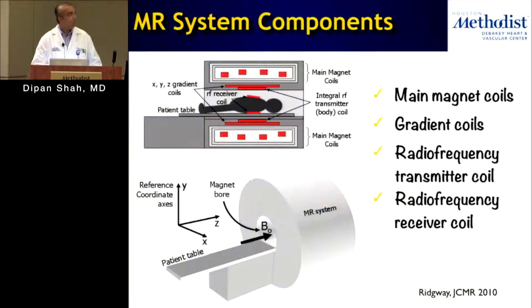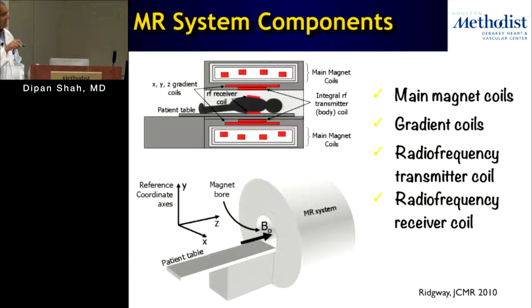I'm going to walk you through the components of an MRI system. It's important to know the terminology. The inside of the scanner is called the bore — the magnetic bore — and that's where the patient goes. We also have a reference coordinate system: an XYZ coordinate system where Z is the head-to-foot direction, and X and Y are within-plane directions.